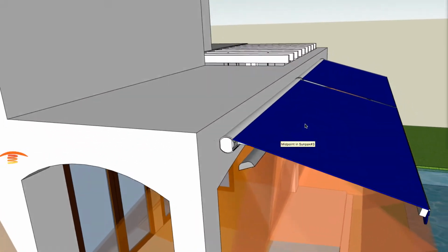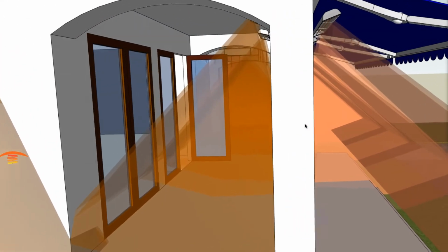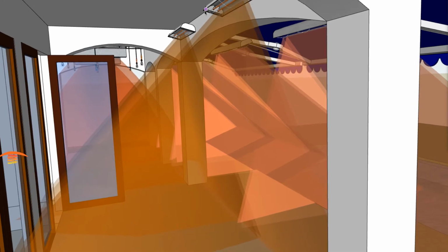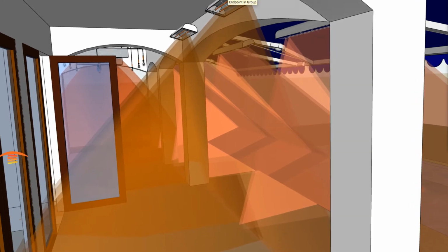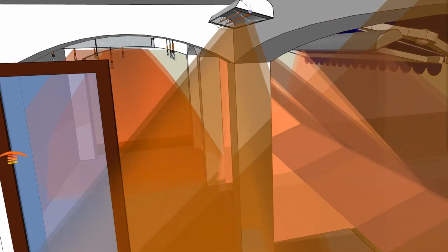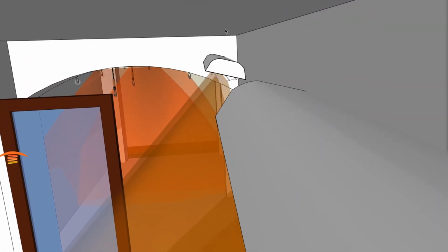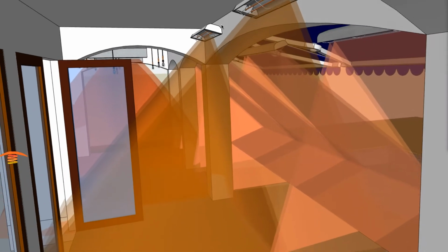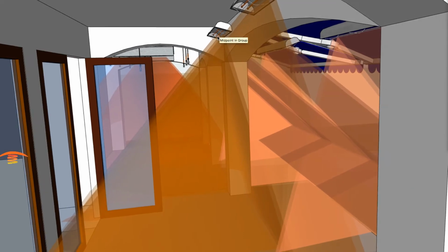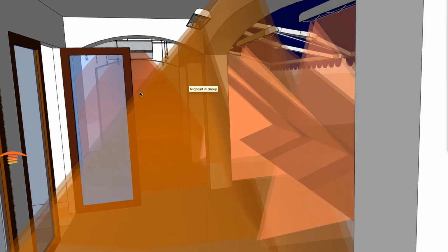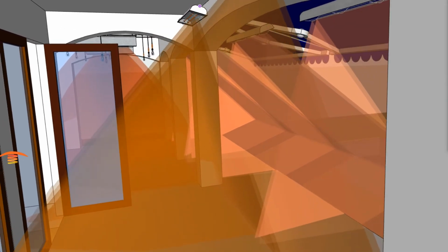Looking at the covered area, what I've done here is taken some WD 5024 heaters. They're 39 inches long. We have 6 inches of clearance on the top edge of the heater. We have 6 inches of clearance on the back side of the heater from the structure itself. And we're not placing the heater right above this doorway. I believe the clearance would have to be 48 inches from the heater's face to the actual doorway.